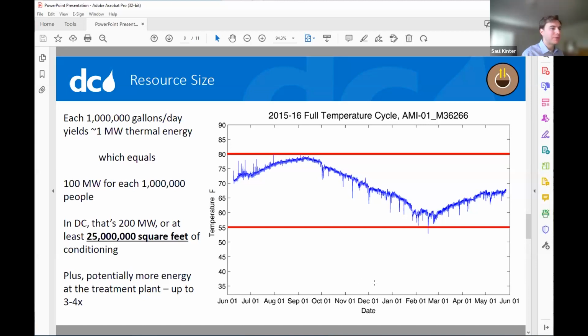Our coldest air temperatures are in late December and January, but we see the coldest sewage temperatures in maybe mid-February. That's convenient from a thermal energy perspective because it means you get a few extra degrees of advantage versus what the top-line cycle numbers would suggest. So when you actually have the hottest air temperatures, you're not at 78, you're at more like 76 - an extra 2 degrees of efficiency advantage.